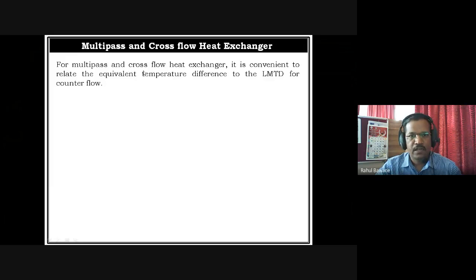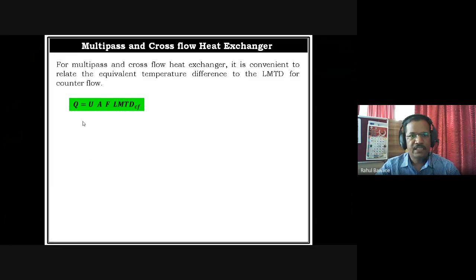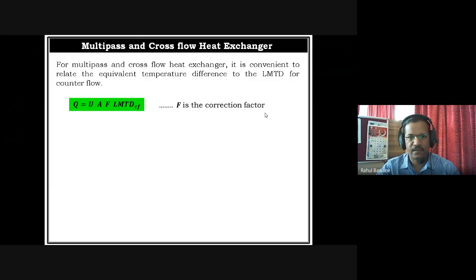For multi-pass and cross flow heat exchangers, it is convenient to relate the equivalent temperature difference to the LMTD for counter flow. Whenever we analytically solve a numerical for this kind of heat exchanger, we always consider LMTD for counter flow, never for parallel flow. The mathematical expression is Q equals U times surface area times F times LMTD for counter flow, where F stands for correction factor, because this is not an exact counter flow heat exchanger but we are taking LMTD for counter flow, so somewhere we need a correction factor.